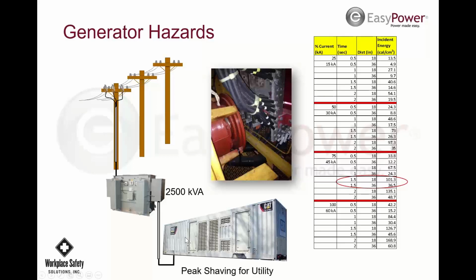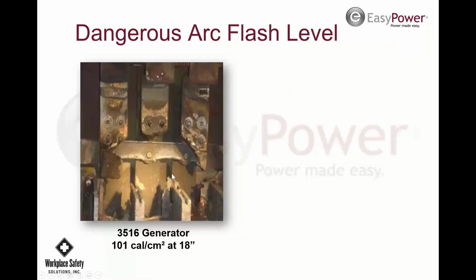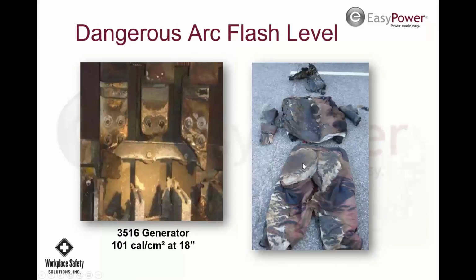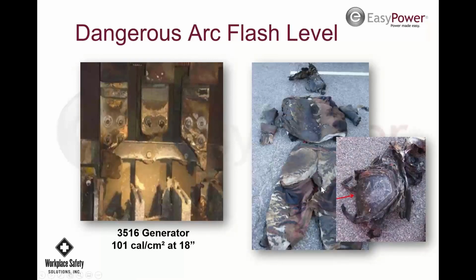So when you want to test, verify, de-energized, there's a little cover on the back, and you can do that and maintain 3 feet by using a 3-foot stick to test. So that's all good. But what would happen if that really actually happened? This is a 3516 generator. It's the same generator as what you just saw, 2 megawatt generator. You can see all the molten metal is gone. That would have happened right in front of his face. And then to see what the suit looked like, if he was wearing a 40 calorie suit, that's what it looks like in that kind of an arc flash. Now the person that was wearing this suit was in the hospital for 1 week and released. So that suit did its job, did what it needed to do. But it's a pretty serious arc flash, and people just need to realize that.